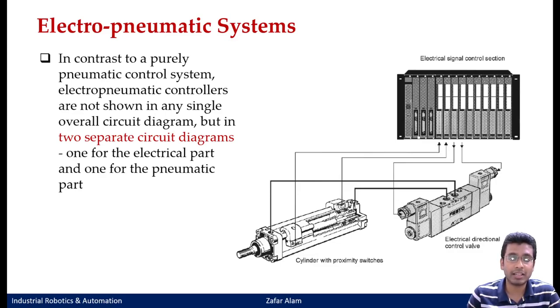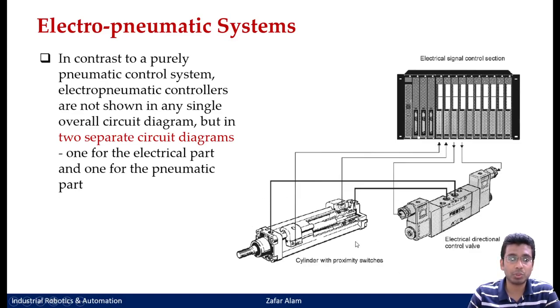One diagram is your electrical circuit control diagram and the other is your pneumatic diagram, basically related to your power elements. If you see in this picture, you can see the dark lines — your double acting cylinder getting connected to this 5 by 2 double solenoid valve. This portion will constitute your pneumatic portion of the diagram. However, all your controls — when you have to extend the cylinder, when you have to retract back — all your input elements and processing will be included in your electrical portion of the diagrams.